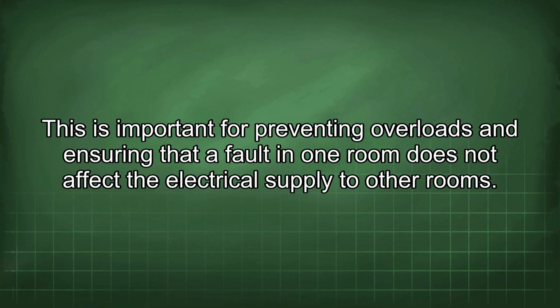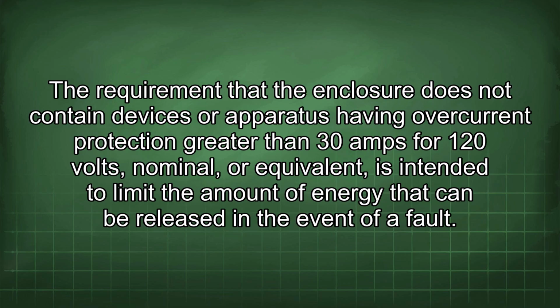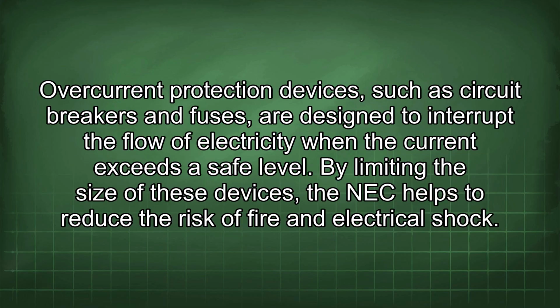The requirement that the enclosure does not contain devices or apparatus having overcurrent protection greater than 30 amps for 120 volts, nominal or equivalent, is intended to limit the amount of energy that can be released in the event of a fault. Overcurrent protection devices, such as circuit breakers and fuses, are designed to interrupt the flow of electricity when the current exceeds a safe level. By limiting the size of these devices, the NEC helps to reduce the risk of fire and electrical shock.